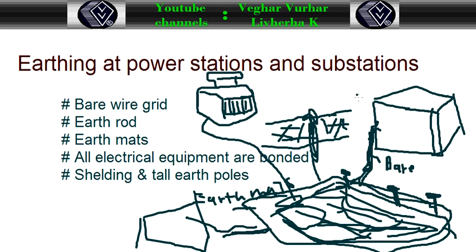There will be a shield on the substations or power station to protect it against lightning. If there's a lightning strike, it will strike here and then run through the earth to the earth rod. The shielding protects the substation against lightning. If lightning strikes the substation and it's not connected here, it can burn every equipment. But this one would run towards the earth mat.